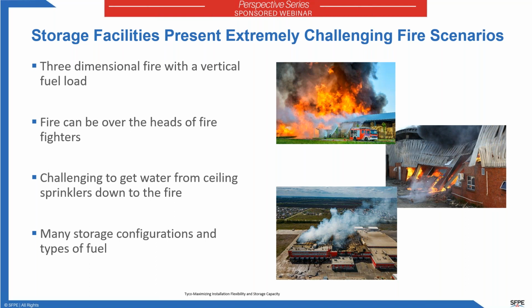So storage facilities, as I said, have lots of challenges. Right? You have three-dimensional fires. They're side to side and they go up. And warehouses are built to store things, and they can store just about anything. And they can be rather tall facilities. So fighting fires that can be over the heads of firefighters can be extremely challenging. Depending on the ceiling height, it can also be very challenging for the water to get from higher up on the ceiling down to the floor, down to where the fire is located, and be able to address it adequately. And there are so many types of storage configurations and types of commodities that could be in a warehouse.